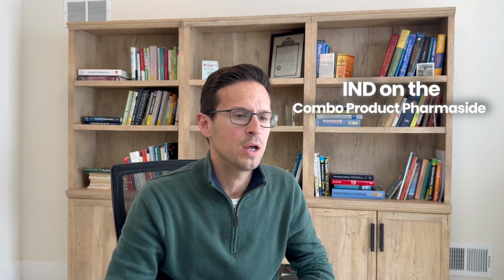A general rule of thumb to go through this full design control and risk management process, including your pre-V&V testing, your engineering study loops, defining your requirements, going through V&V, human factors, you need at least a year and a half, right? At least a year and a half. And depending on how many design iterations you have to go through, it's just going to expand. So standard off-the-shelf product, minimum year and a half. Even if you're trying to get to a clinical trial, like an IND on the combo product pharma side, or an IDE on the device side, you're going to need about a year and a half minimum to go through this process. I think that's a good takeaway.